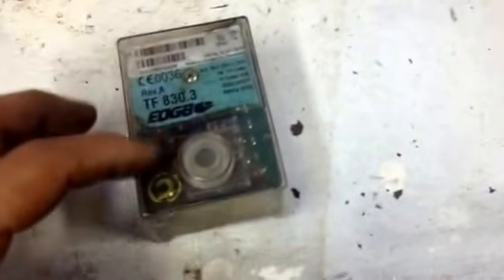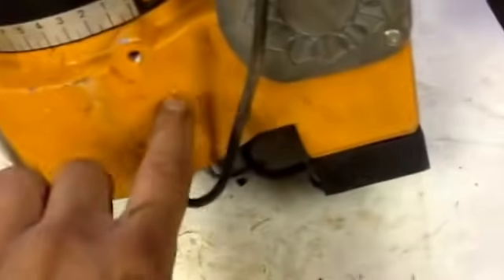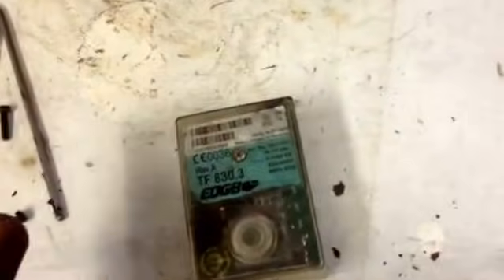One trick that professionals quite often do is they'll have one of these boxes built up without any of the guts in it. All it has is a series of little switches, because that's all this is doing. The first thing this box does is switch on the fan, so they'll have a switch for fan. Then a switch for spark, and they'll power up the spark generator. It'll then switch on diesel flow, and then it'll go. Do you see what I mean? So you can check if it's running by fitting a series of switches. This is only for test procedure because, good God, if you left it running like that, someone's going to die.